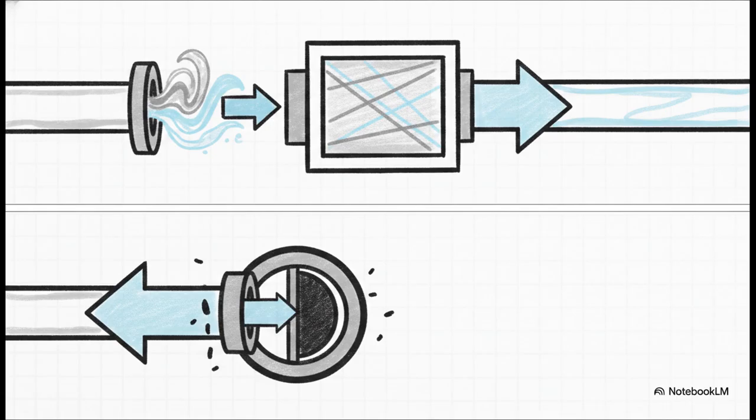The exact same rigorous logic applies to compressed gases. Things like nitrogen or air aren't just piped into the room and forgotten about. Any compressed gas touching the product or contact surfaces has to be pushed through point-of-use sterilizing grade filters. And you absolutely cannot just install them and forget them. These filters must be routinely integrity tested according to a documented risk-based schedule. Furthermore, vacuum and other services have to be rigorously assessed to prevent back contamination. Think about it. If a vacuum system pulls air, you must ensure there is absolutely no pathway for contamination to travel backwards into your clean environment.